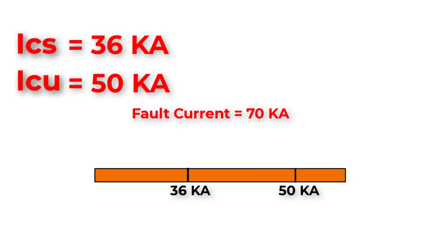Now if the fault is equal to 70 kilo-amperes, which is above ICU, the breaker will not be able to handle this fault current. That will cause rupture to the breaker and the complete circuit, and could also cause a fire. So be extra careful.